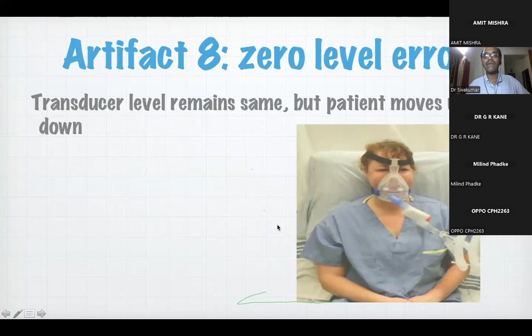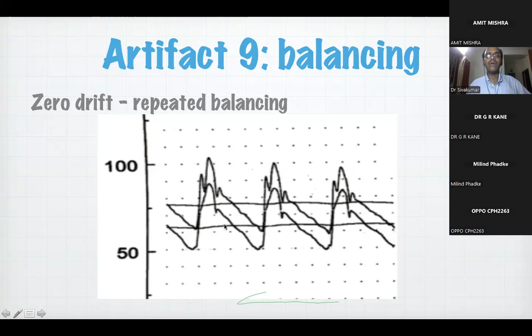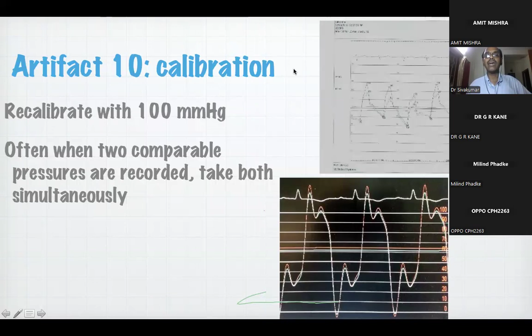Balancing artifact. Of the two pressure transducers that you are using, one is not balanced, so one sort of drifts. This is called the zero drift. So the zero drift is actually a balancing error, and here you again recalibrate and balance. Calibration error: the same pressure curve, if you put it in two transducers, will result in two different readings. So this is basically an abnormality in the calibration. Again, you have to recalibrate the machine.